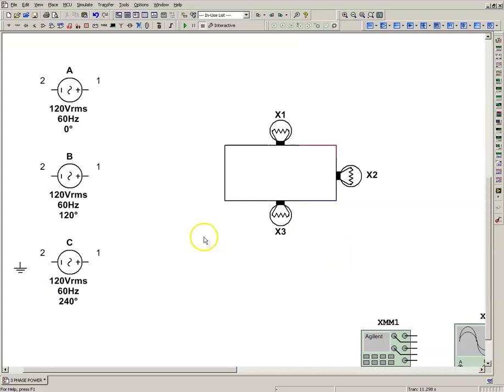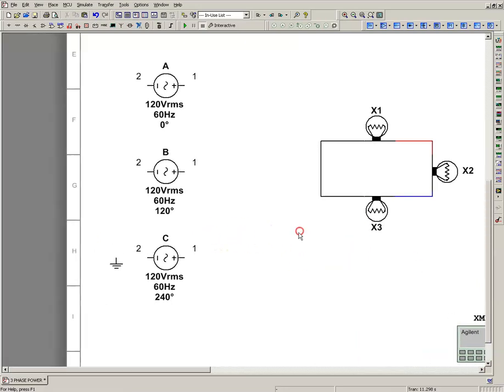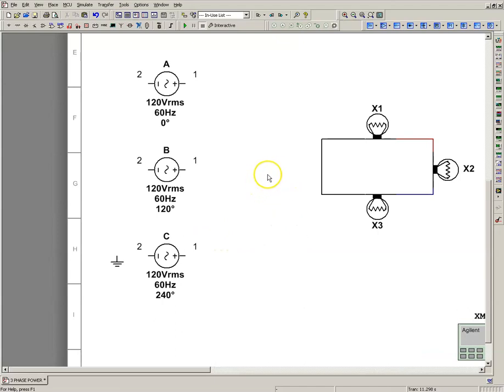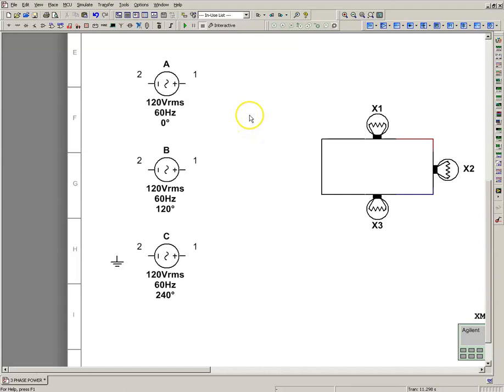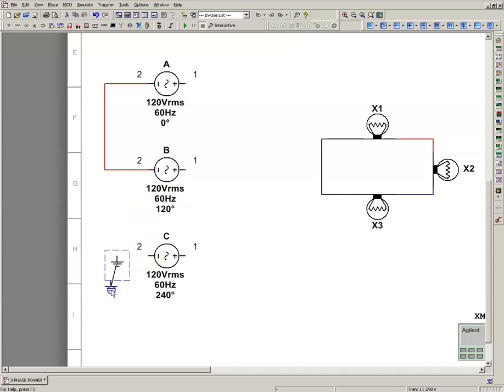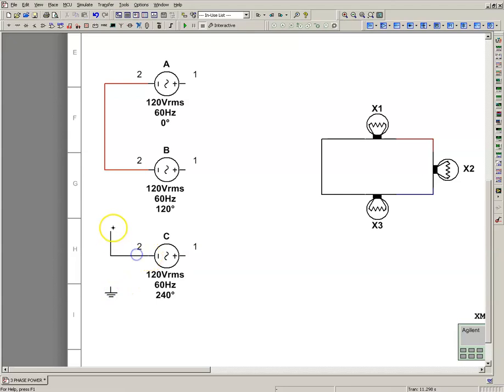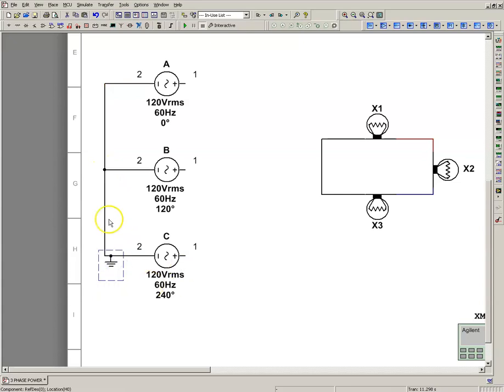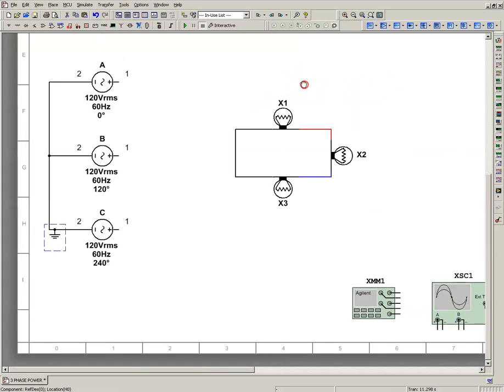Now we're going to connect them. There's two ways we can connect three-phase supplies: delta or Y. Typically in a building system it's fed from a Y, which would be a Y secondary on a transformer. I'm going to connect all of my pin two locations together. Bear with me as I do this - we're going to have a Y source when I'm finished.